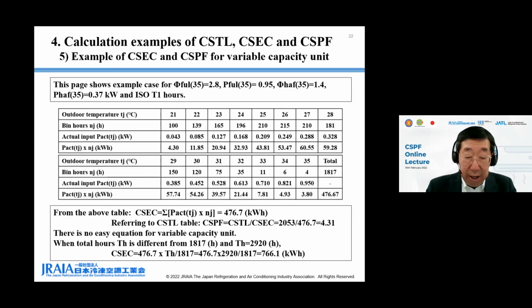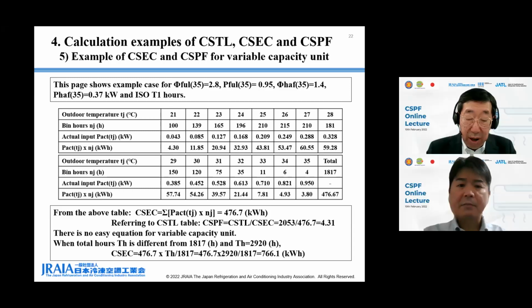In this table, the first line shows outdoor temperature TJ. The second line shows ISO T1 bin hours at each TJ. The third line shows actual input at each TJ, which can be calculated as shown in the example of actual ER for variable capacity unit. The fourth line shows the actual input in the third line multiplied by bin hours in the second line, and the total of this line becomes cooling seasonal energy consumption CSEC. From this table, CSEC is 476.7 kilowatt hour as shown in the lower right-hand row.